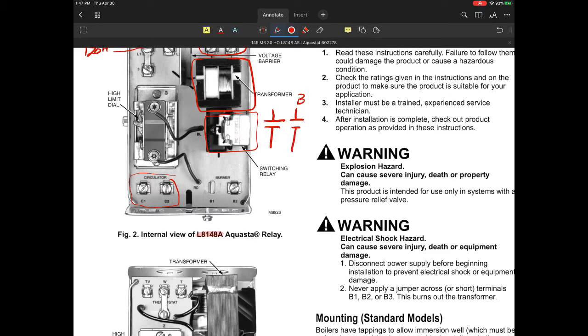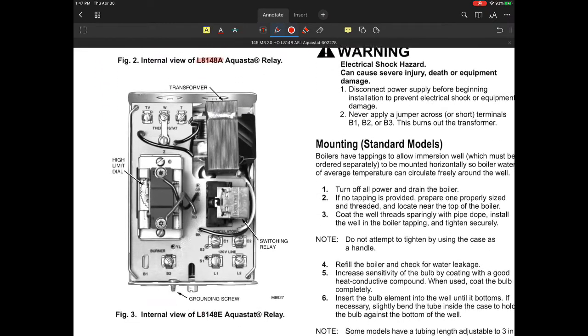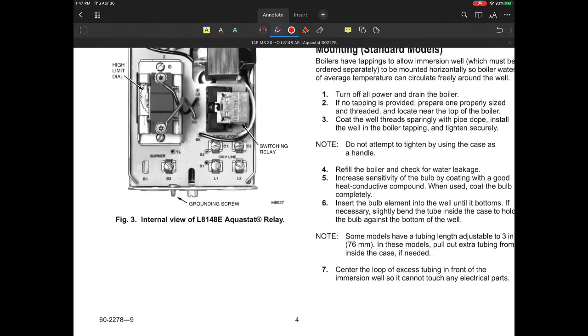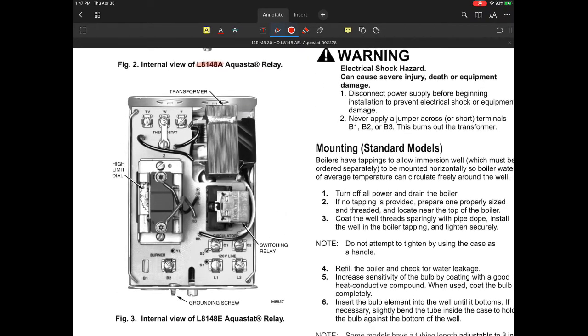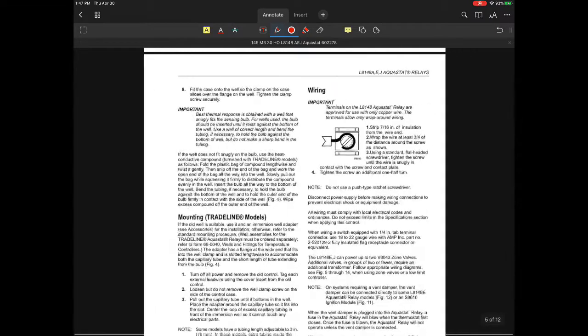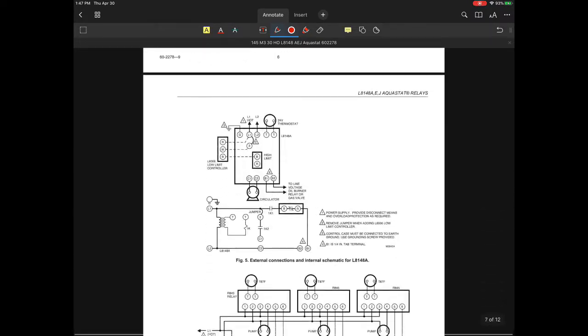Your circulator terminals: earlier we talked about the relay contacts that are in there. One of these is going to be for the burner circuit, and one is going to be for the circulator circuit. The circulator circuit feeds power directly to the C1 terminal from this. So this would maybe go to C1, and this would of course go to B1. And we'll see the internals of this. This right here is the actual high limit control, the part that the sensing bulb actually goes to on this device.